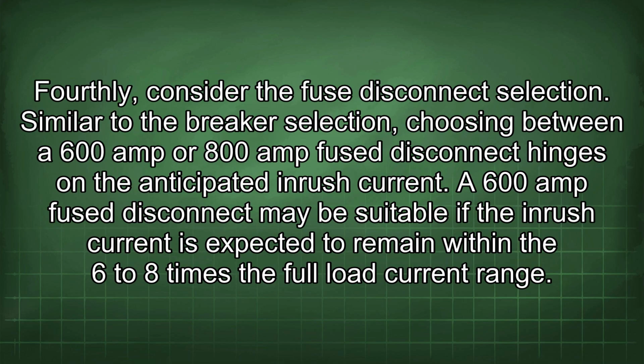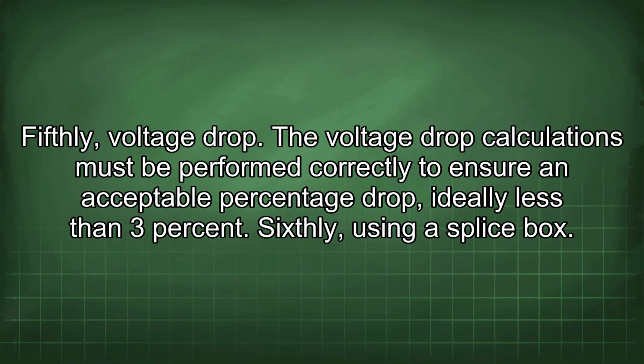Fourthly, consider the fuse disconnect selection. Similar to the breaker selection, choosing between a 600 amp or 800 amp fuse disconnect hinges on the anticipated inrush current. A 600 amp fuse disconnect may be suitable if the inrush current is expected to remain within the 6 to 8 times the full load current range. Fifthly, voltage drop. The voltage drop calculations must be performed correctly to ensure an acceptable percentage drop, ideally less than 3%. Sixthly, using a splice box.